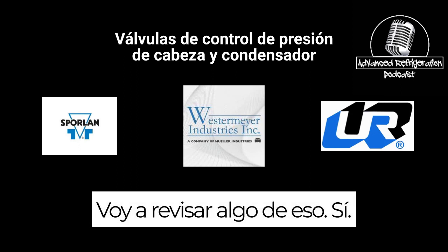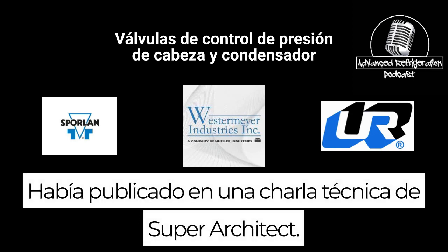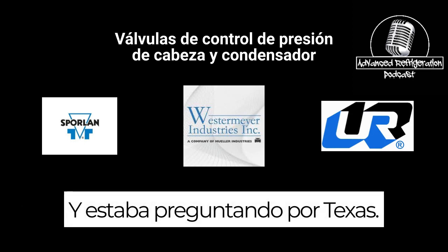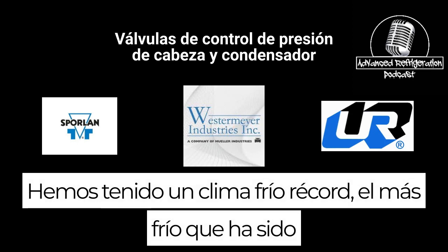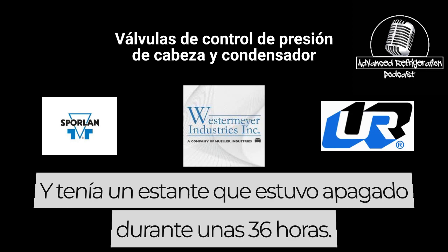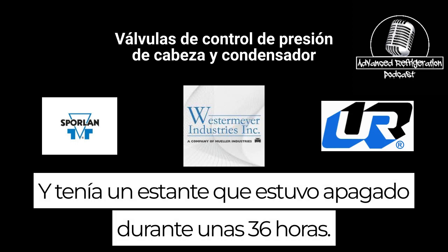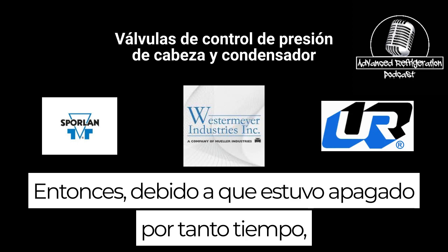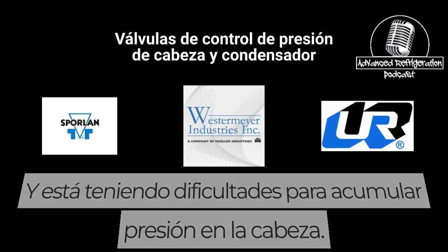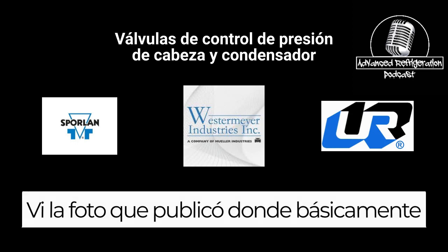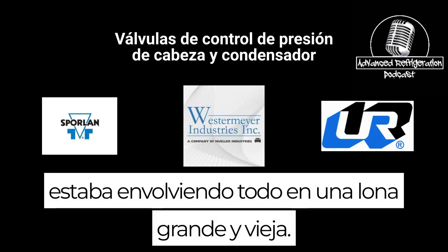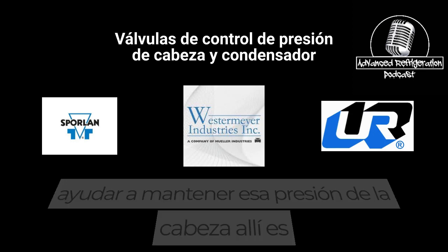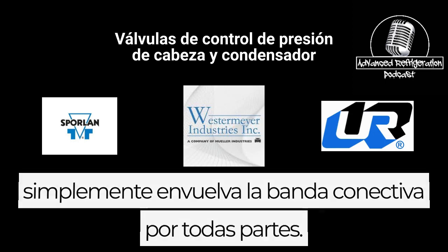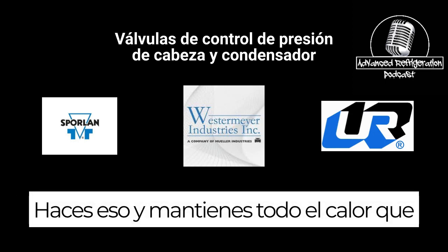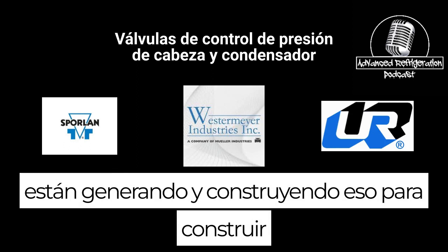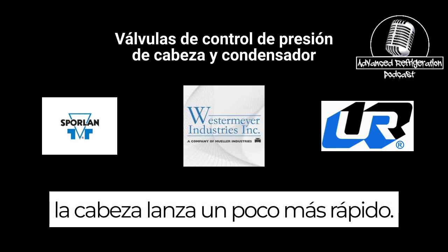I'm going to shout out somebody. Yeah, that would be a good one. He had posted on Supermarket Tech Talk, asking about Texas, where we've had record cold weather. This is the coldest it's been in probably 30 years down here, if my understanding is right. He had a rack that was off for about 36 hours, so because it was off for so long, the refrigerant doesn't want to leave anywhere, and he's having a hard time building up head pressure. I saw the picture he posted where he was wrapping everything in a big old tarp. But one of the things you can do to help keep that head pressure in there is just wrap the condenser fan shroud. It'll keep all the heat that you're generating and build up the head pressure just a little bit faster.